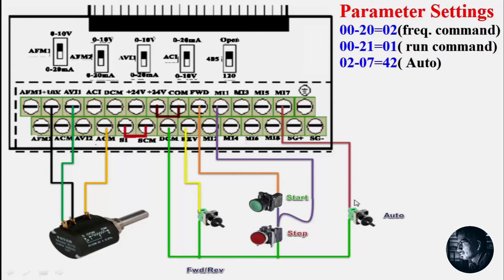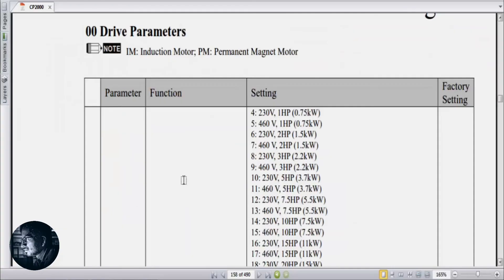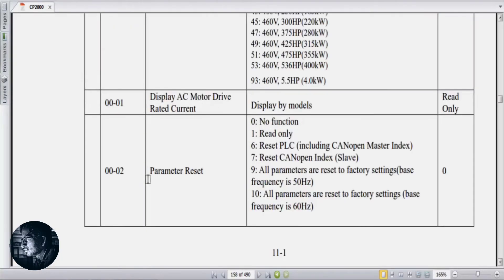Now the wiring is complete. Moving on to the parameters — first we will reset all parameters to default values. To reset to default, set parameter 00-02 to 9.